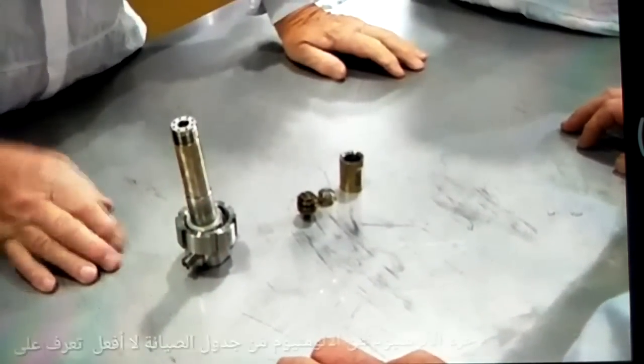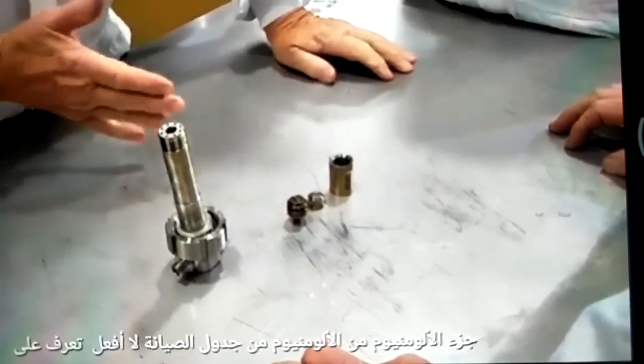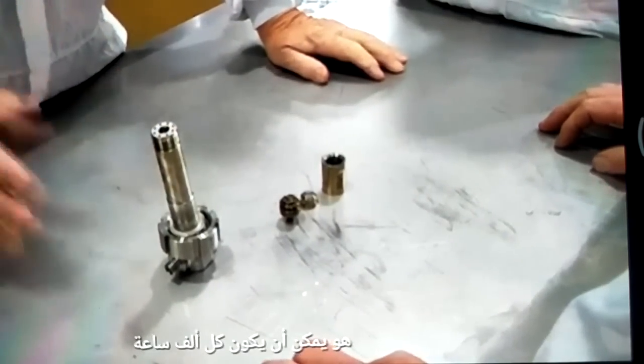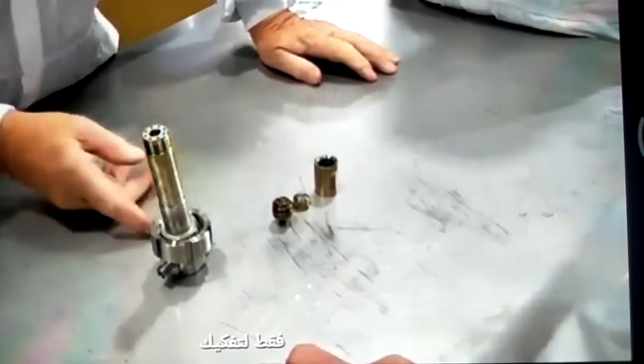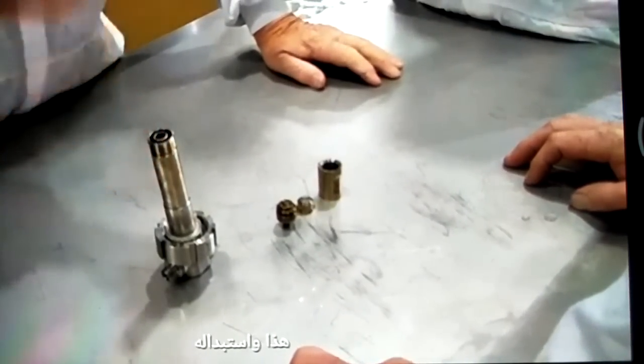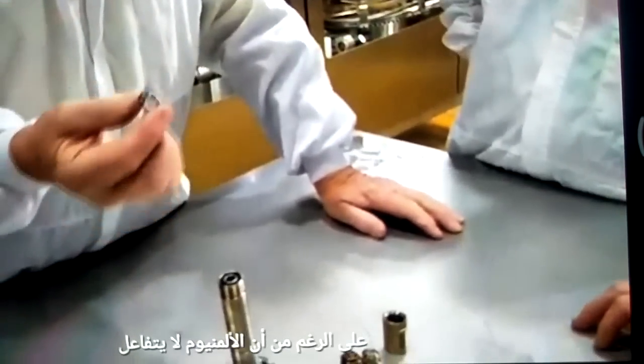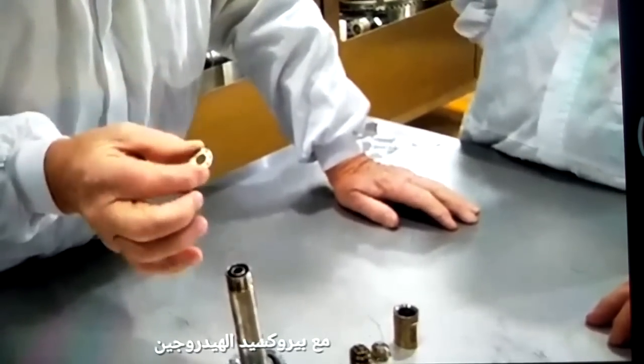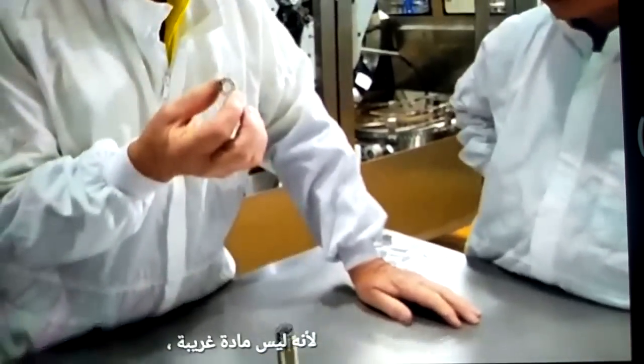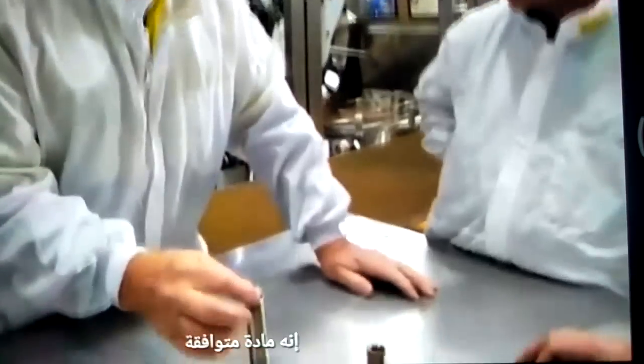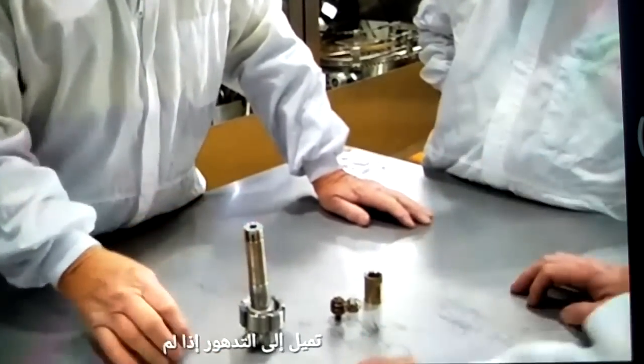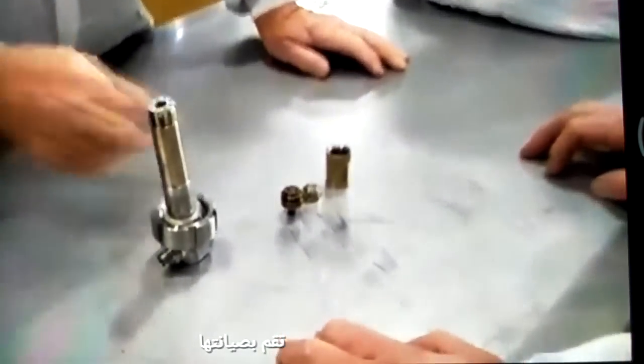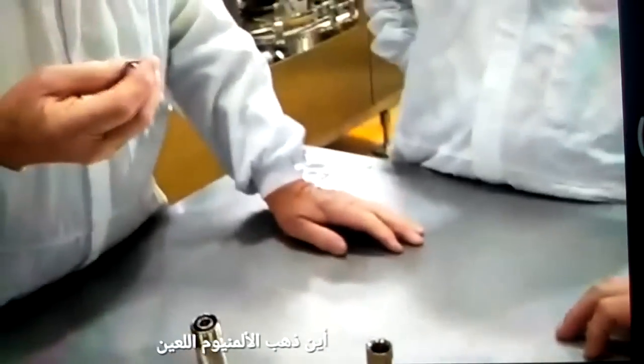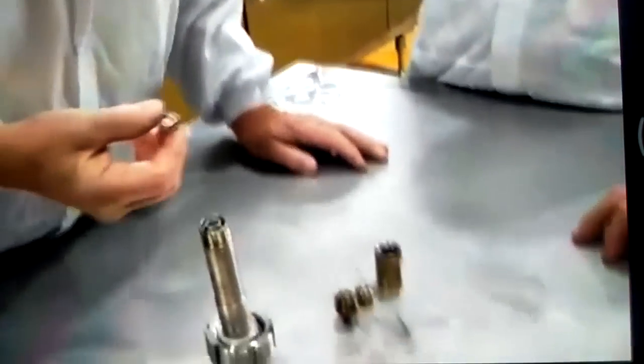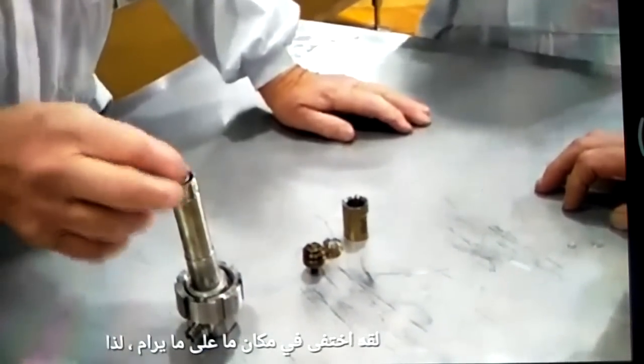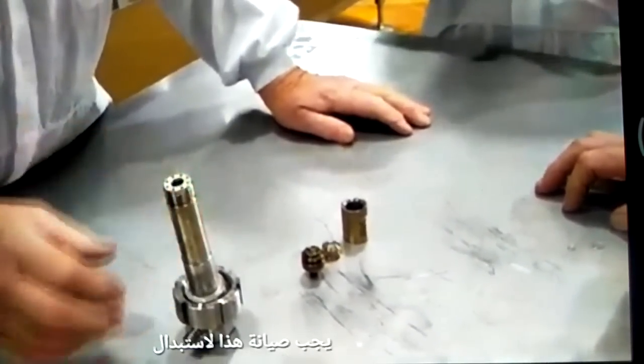Aluminium. Part of the servicing schedule, I don't know what it is. It could be every 1,000 hours, to dismantle this and replace this. Even though aluminium does not react with hydrogen peroxide because it's not an alien substance, it's a compatible substance, it tends to deteriorate if you do not service it. One day you will open this and say, where's the aluminium gone? It's gone somewhere. Okay? So this needs to be serviced to replace this.